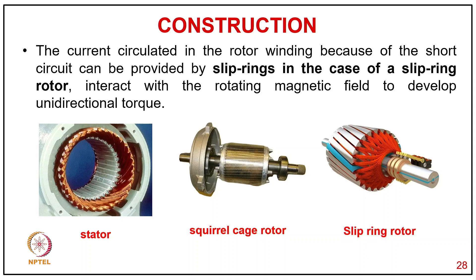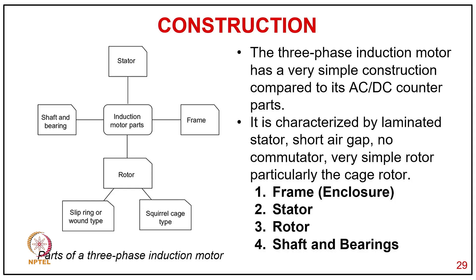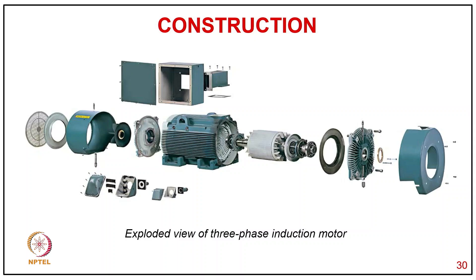The current circulated in the rotor winding due to the short circuit provided by slip rings (in the case of slip ring rotor) interacts with the rotating magnetic field to develop unidirectional torque. The physical construction includes the stator, shaft and bearing, frame, and both slip ring rotor and squirrel cage rotor. The three-phase induction motor has a very simple construction with laminated stator, short air gap, no commutator, and particularly simple squirrel cage rotor.